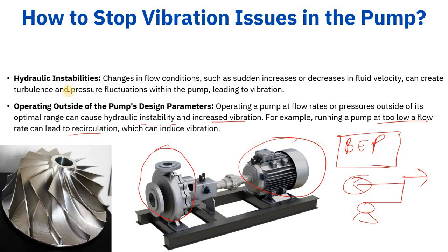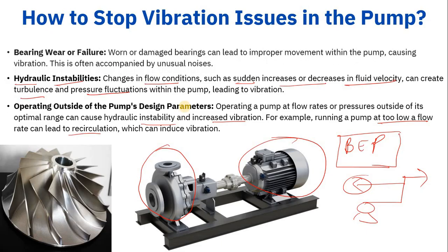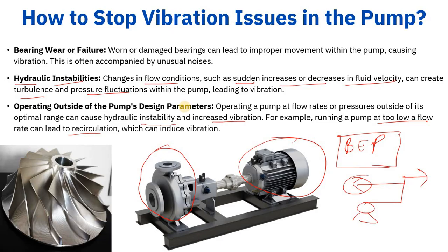Hydraulic instabilities occur when flow conditions change suddenly — such as a rapid increase or decrease in flow velocity — creating turbulence or pressure fluctuations within the pump that lead to vibration. This happens frequently in plants. Bearing wear or failure is another cause: if bearings are worn or damaged, they cause improper movement within the pump, creating vibration often accompanied by unusual noises.